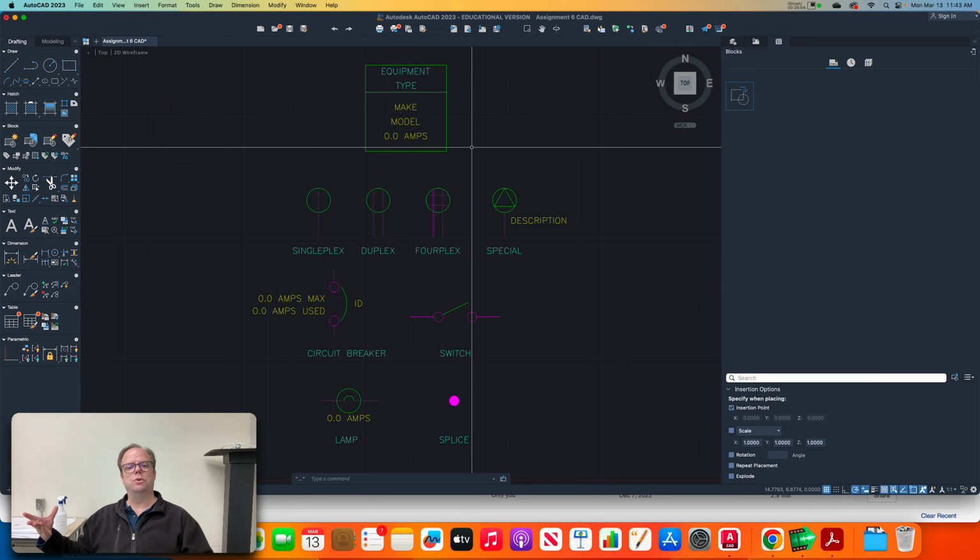What you want to do, for purposes of making sure that you don't trip the breakers, is find out what the worst case scenario is. If I crank this thing up to 11 and say, do all the things in the most demanding way that you could do all those things, and that was happening, how many amps would it be drawing off that circuit? That's the number you want to put in there.